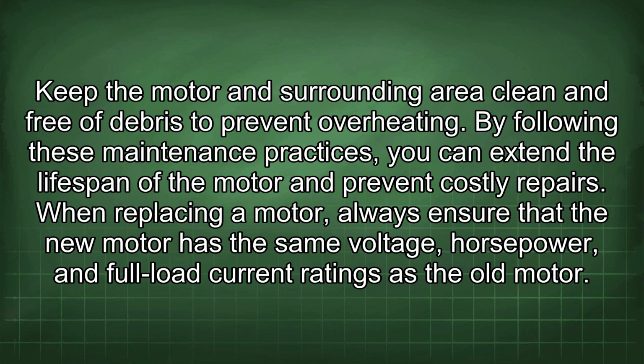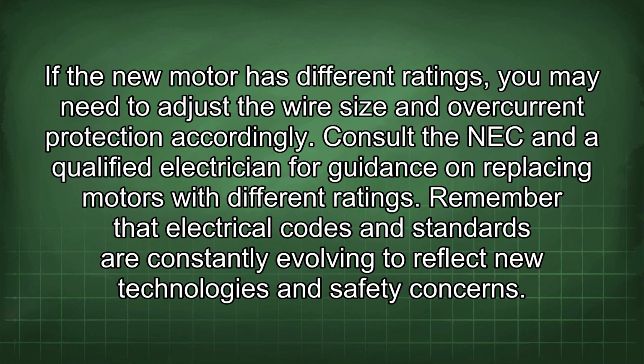When replacing a motor, always ensure that the new motor has the same voltage, horsepower, and full load current ratings as the old motor. If the new motor has different ratings, you may need to adjust the wire size and overcurrent protection accordingly. Consult the NEC and a qualified electrician for guidance on replacing motors with different ratings.